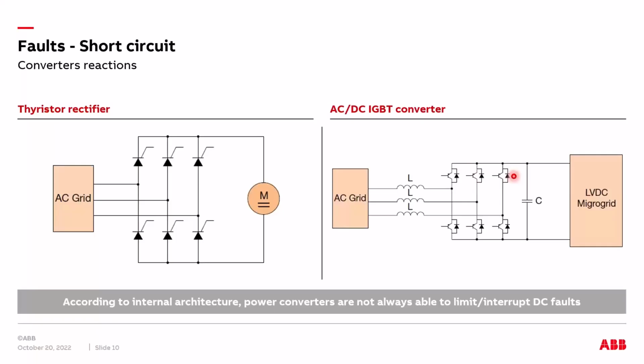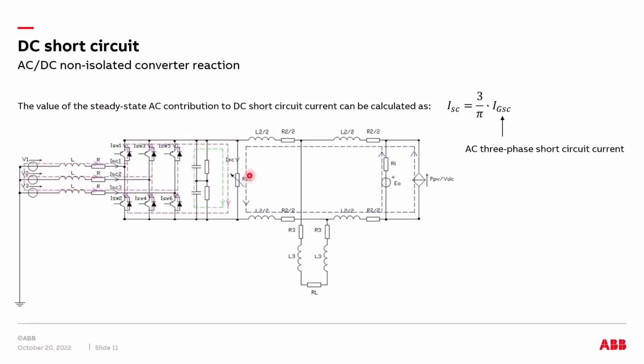You know, we can control the IGBTs since they are semiconductor devices. Basically, they can be controlled both in open and in closed position, but diodes cannot be controlled. So imagine having a short circuit on the DC side of our DC distribution system. Then we can have an overall load, or like in our case, more than one battery installed in parallel, here represented by a voltage generator in series with the internal resistance. And we can also have, for example, a photovoltaic system installed in our DC distribution system in order to supply locally the requested power or part of the requested power.